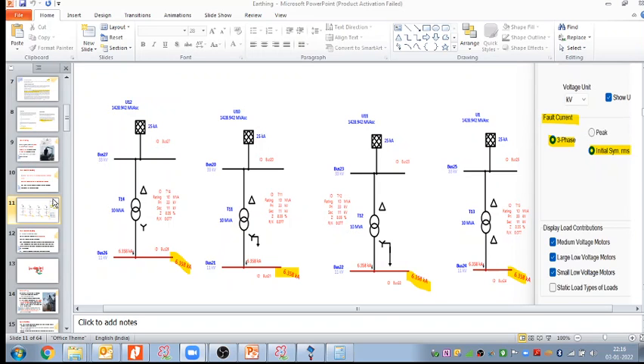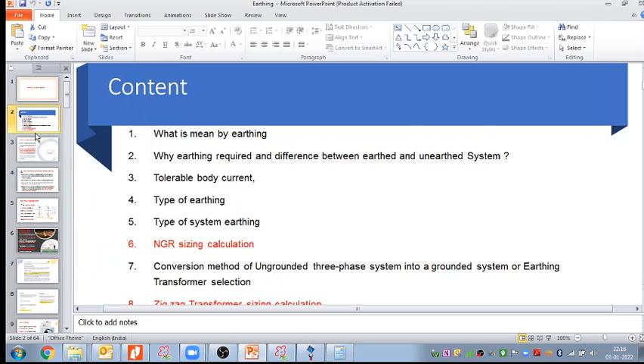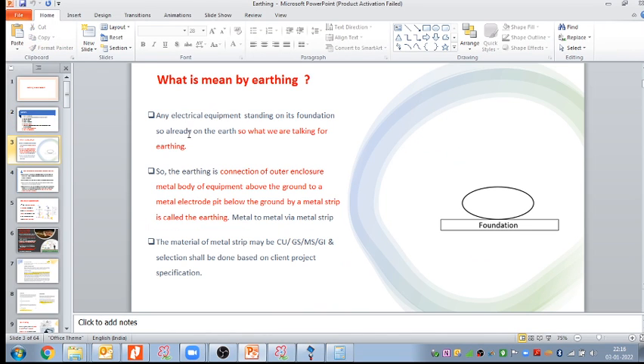So let us conclude what we discussed so far. What is meant by earthing? This is clear to everyone. Equipment is standing on its foundations, so it is already on the earth. So what are we talking about for earthing? Earthing is the connection of the outer and enclosing metal body of equipment above the ground to a metal electrode pit below the ground by a metal strip. That is called earthing. Metal to metal via a metal strip is called earthing. The metal of the strip may be copper, GS, MS, GI. Based on the client project specifications we can select.